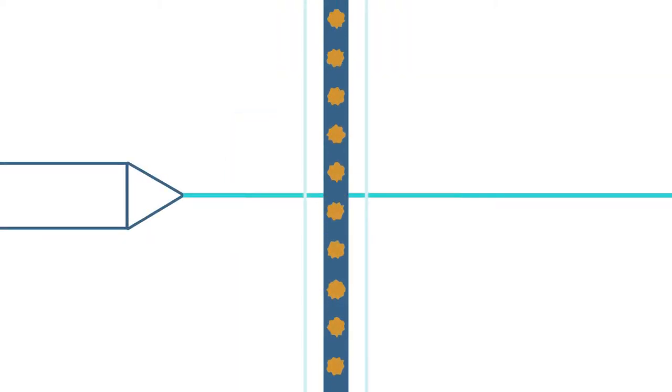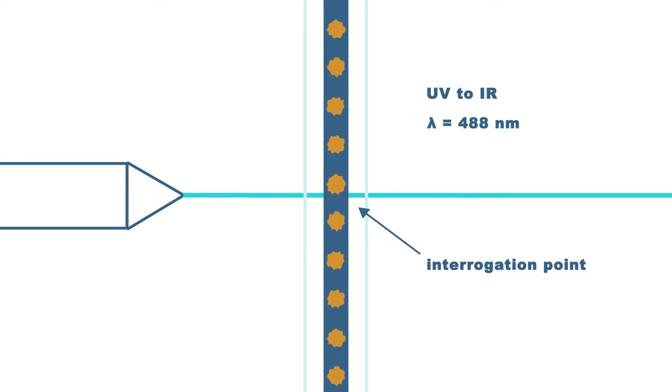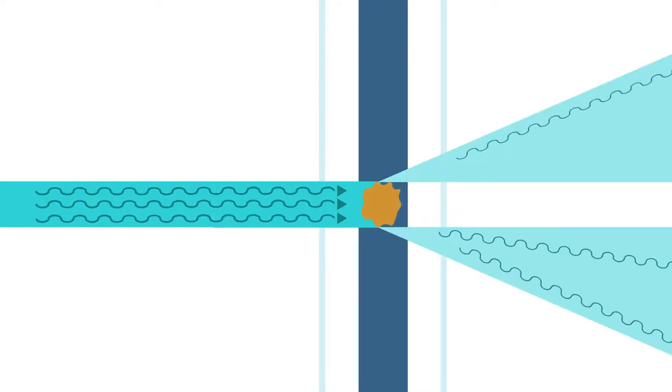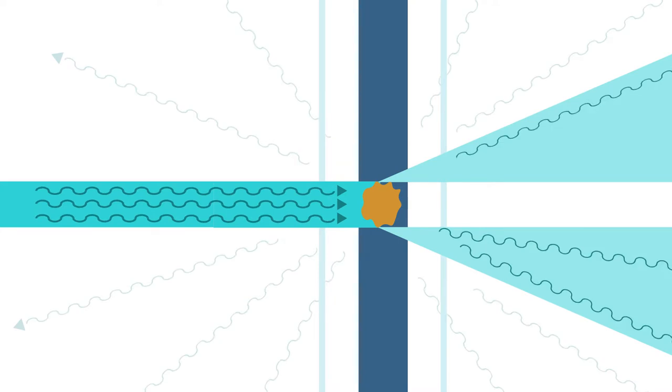Analysis in flow cytometer is performed by up to six lasers in a spectral range from ultraviolet up to infrared. For purposes of simplification, only laser light with a wavelength of 488 nanometers is pictured. This light interacts with bypassed events in the so-called interrogation point. Coherent light interacts with the particulate structures of the events. Dependent on the irregularity of the internal or external structures of an event, scattered light arises into all directions.